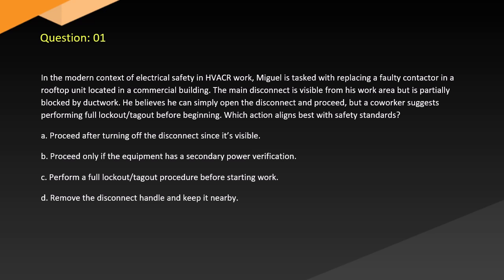Question 1. In a modern context of electrical safety and HVAC work, Miguel is tasked with replacing a faulty contactor in a rooftop unit located in a commercial building. The main disconnect is visible from his work area but is partially blocked by ductwork. He believes he can simply open the disconnect and proceed, but a coworker suggests performing full lockout-tagout before beginning. Which action aligns best with safety standards?